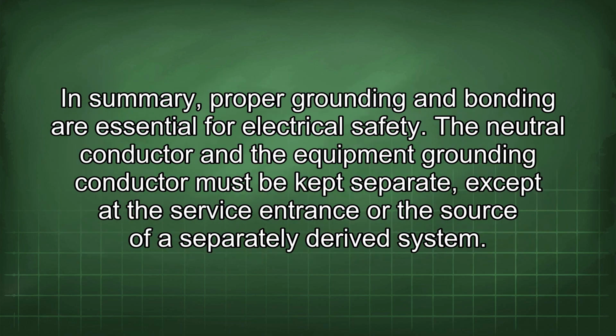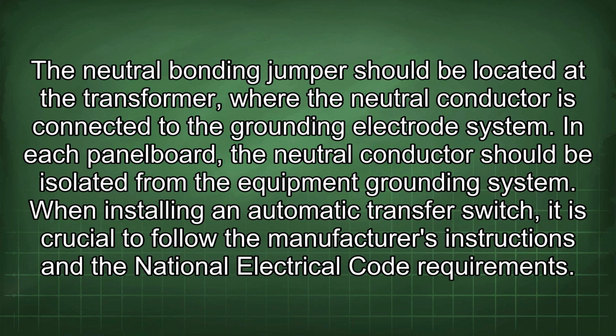In summary, proper grounding and bonding are essential for electrical safety. The neutral conductor and the equipment grounding conductor must be kept separate except at the service entrance or the source of a separately derived system. The neutral bonding jumper should be located at the transformer, where the neutral conductor is connected to the grounding electrode system. In each panel board, the neutral conductor should be isolated from the equipment grounding system.